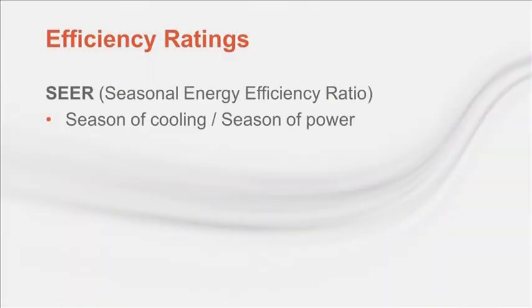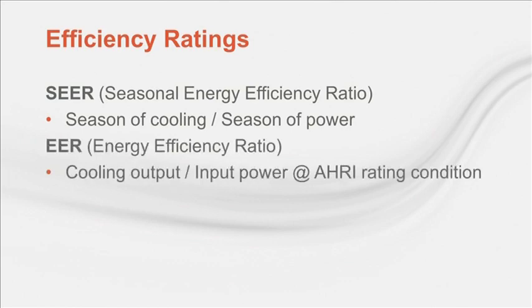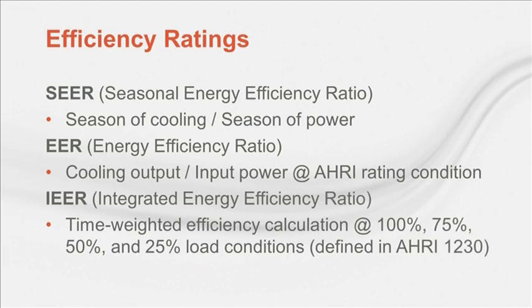SEER is a ratio of a season's worth of cooling produced divided by the same season's worth of energy used. It's sort of a blended efficiency number that attempts to encompass both full load and part load operation. EER is the ratio of cooling output at AHRI standard rating conditions divided by the power consumed at those same conditions. It provides a full load efficiency metric. And IEER is a time-weighted efficiency calculation of 4 load conditions: 100, 75, 50, and 25%. It's an attempt to provide a single number part load efficiency metric.